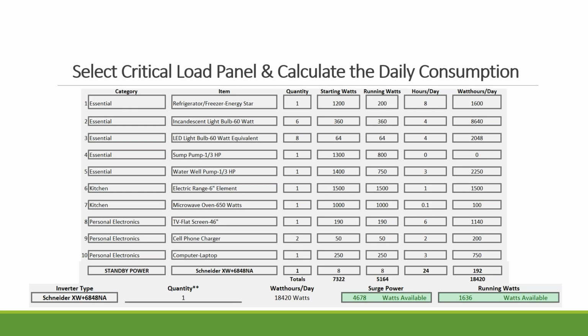So here, for this particular project, that's what we selected. You can see that the total starting wattage requirement is 7.3 kW, and the running wattage is about 5.1 kW. We select one Schneider inverter, and it shows you that you still have some surge capacity and some running wattage available. If it goes over that inverter's threshold, then it will turn red, just to give you a warning. Now, is that critical? Maybe. It is critical if you have everything running at the same time. So the likelihood is low, but again, you do not want to go over too much. Then it could cause a potential issue when clients turn on appliances at the same time, and the inverter can shut off. The total estimated consumption for this home is about 18.4 kilowatt hours.